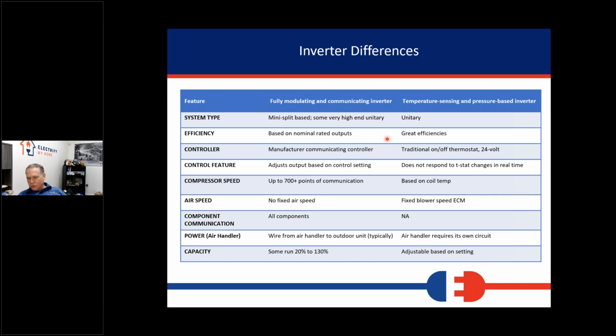Most of these units have ECM motors and they run at one speed. The air handler control requires its own 230-volt circuit, and the capacity is adjustable based on the settings. So generally these units are going to come with two SKUs. There's a 2 and 3 ton unit and a 4 and 5 ton unit, and there's a switch that you flip in there to tell it what capacity you want it to operate at. Really cool technology, really young in the marketplace, but doesn't have all of the advanced features of complete communicating systems.